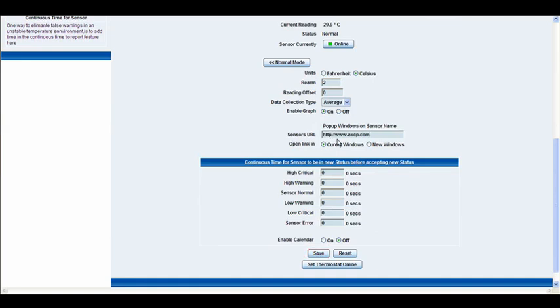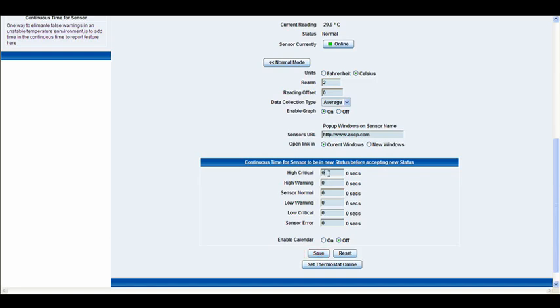Below this we have some other options. Now these all work on the same type of principle. What this essentially does is you can type in the amount in seconds that it has to be in that status before it accepts that new status. So for example, if we type in the high critical here that it has to go into high critical for at least 10 seconds before it will register that it has gone into a high critical status.